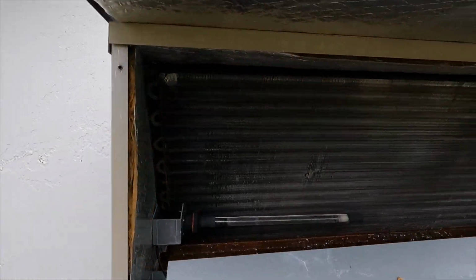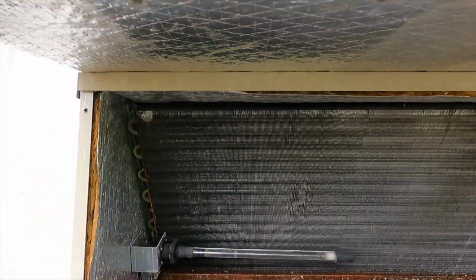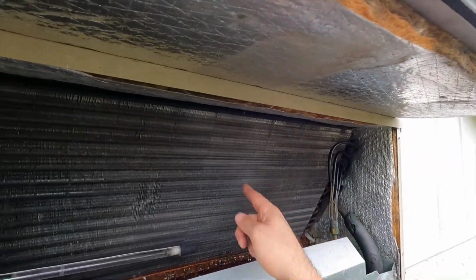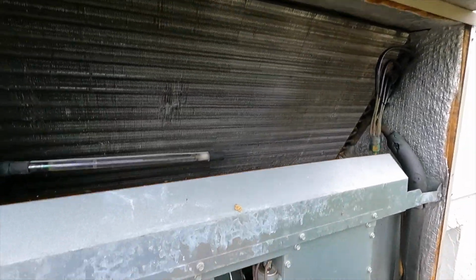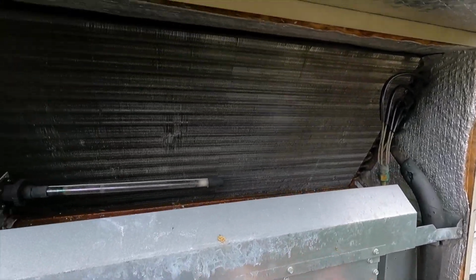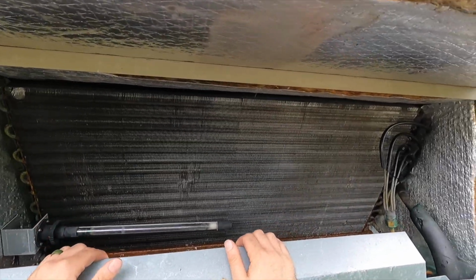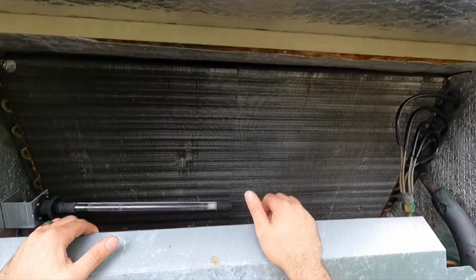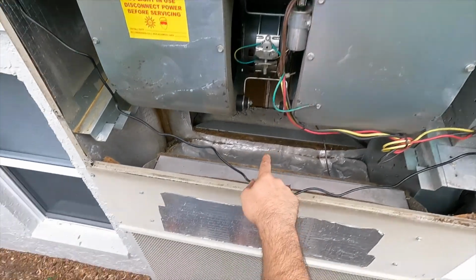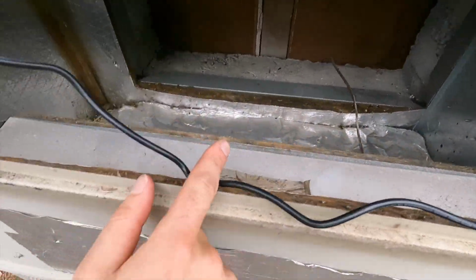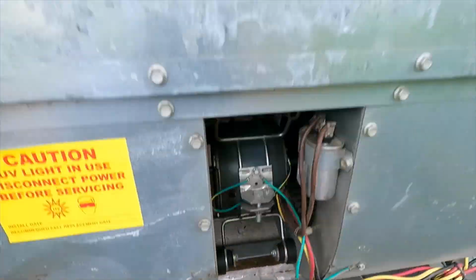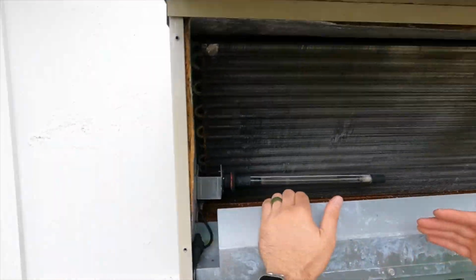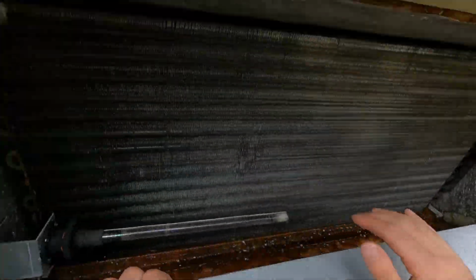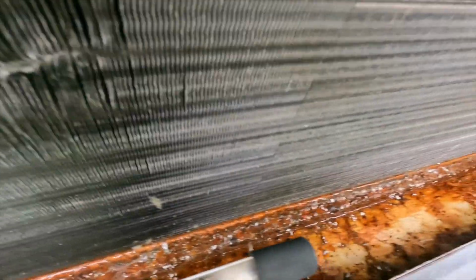Looks like they got a UV bulb here that's burnt out, so we'll make a recommendation on replacing that if they want to keep it. But here is our evaporator coil. Now, with our blower system under our evaporator coil, we effectively have a positive pressure system. So air is being drawn through the house right here through our returns. You can see what I mean when I say there isn't much airflow through the blower housing and then out through the evaporator coil. Now look at that drain pan.